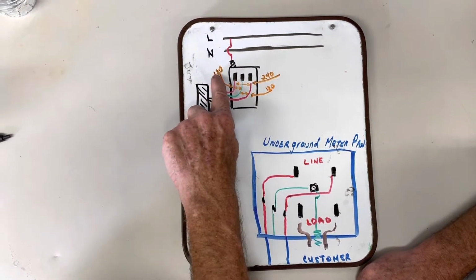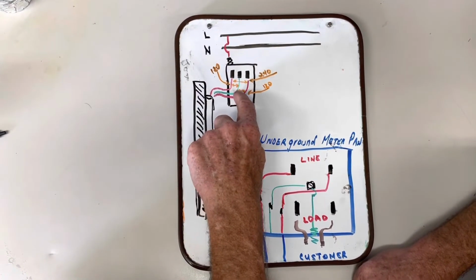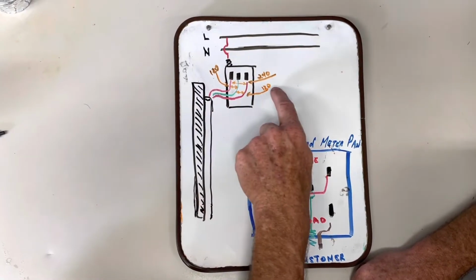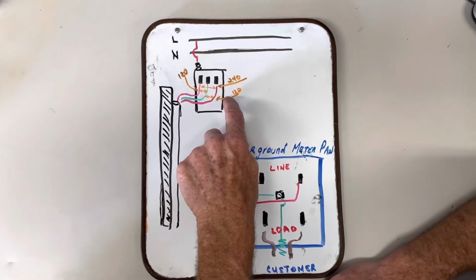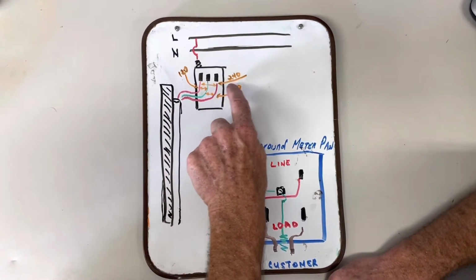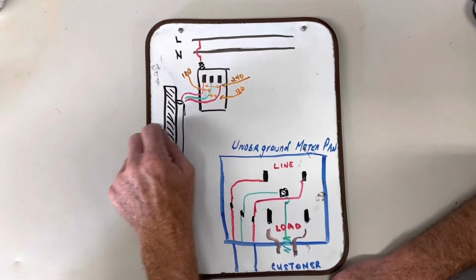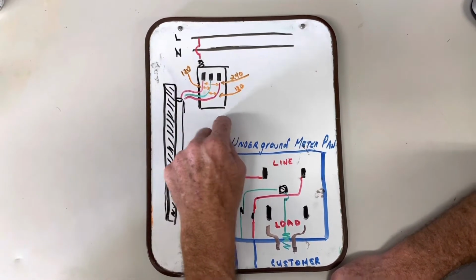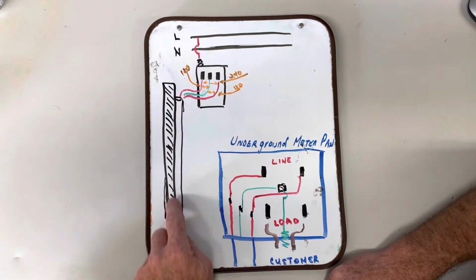If we check voltage, we would go phase to ground, we would get 120 volts. Phase to ground, we get 120 volts. And phase to phase, we get 240. So this is a 120/240 volt service coming down the pole.